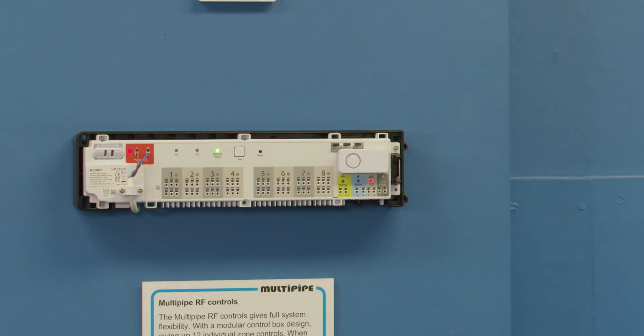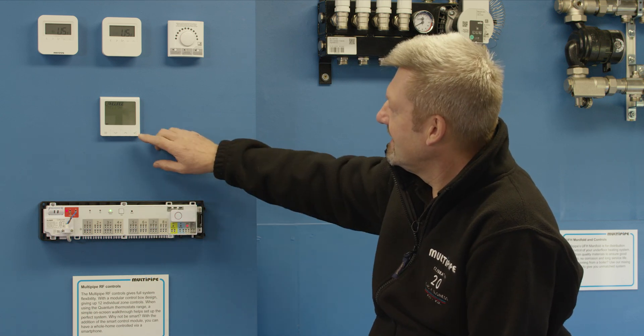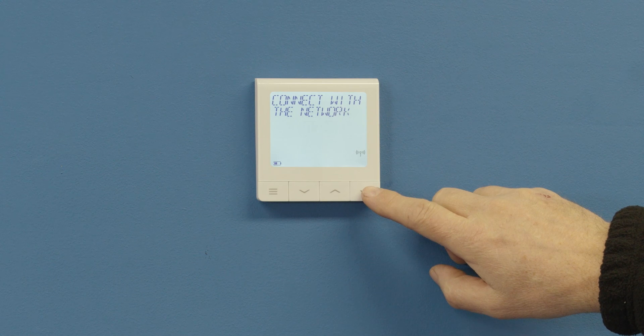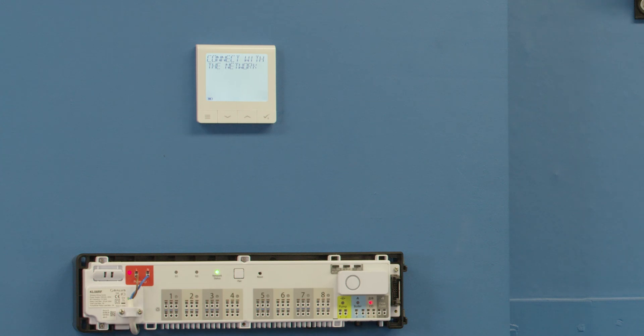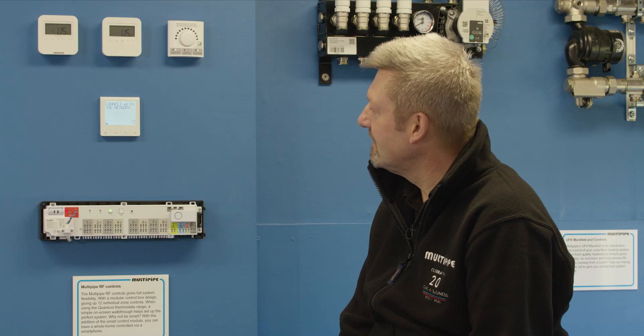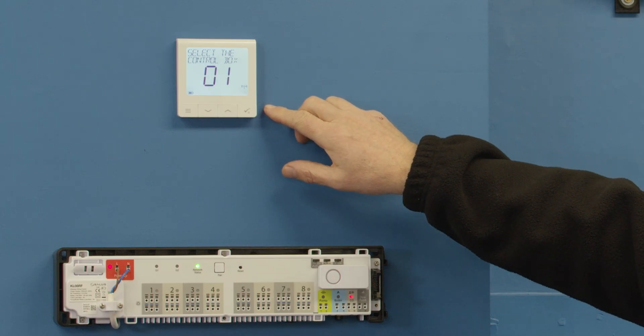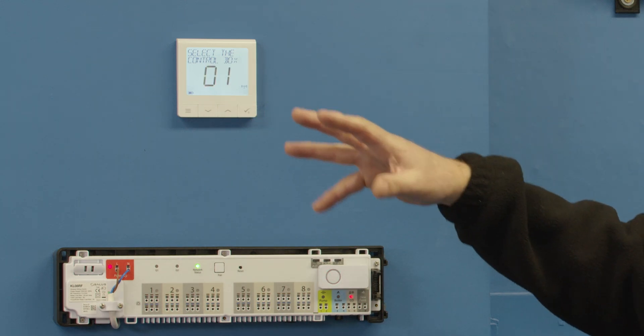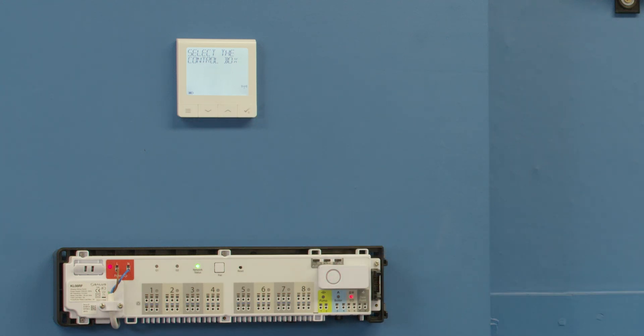The red light is now flashing. We're going to go to our thermostat, press the button once to wake it up and press it a second time. It tells me quite clearly on screen: connect with network. It's now going to pair that thermostat and connect it with the network. It's then going to ask what system we're playing with — if you're looking at underfloor heating, it will default to that automatically, but it can offer a radiator as an option. We press the tick button to confirm underfloor heating.